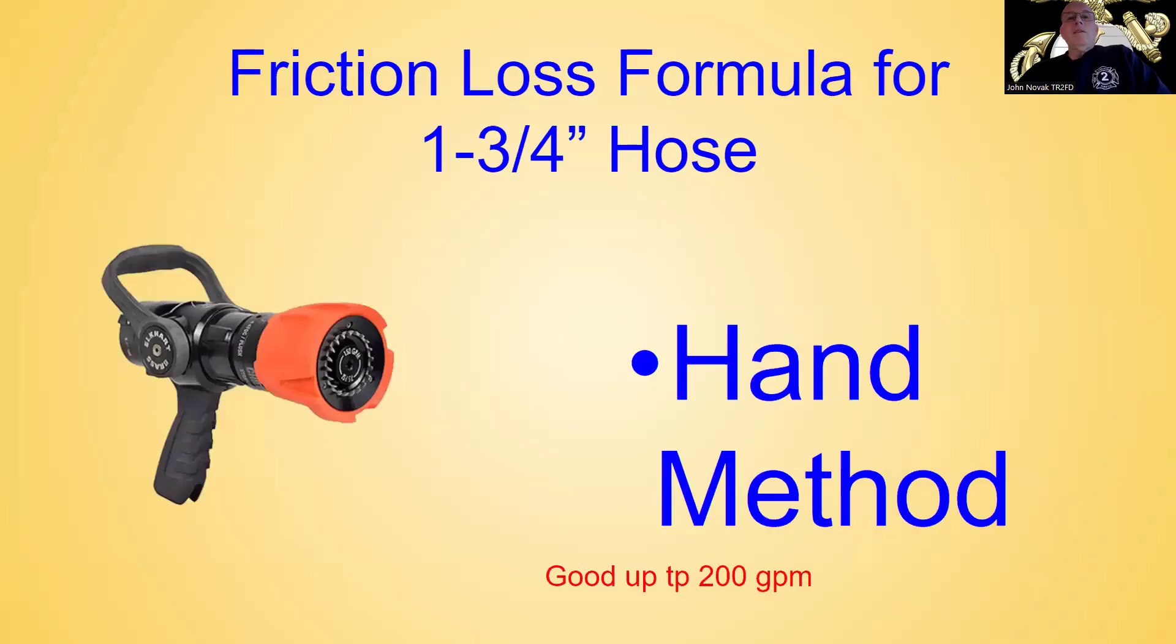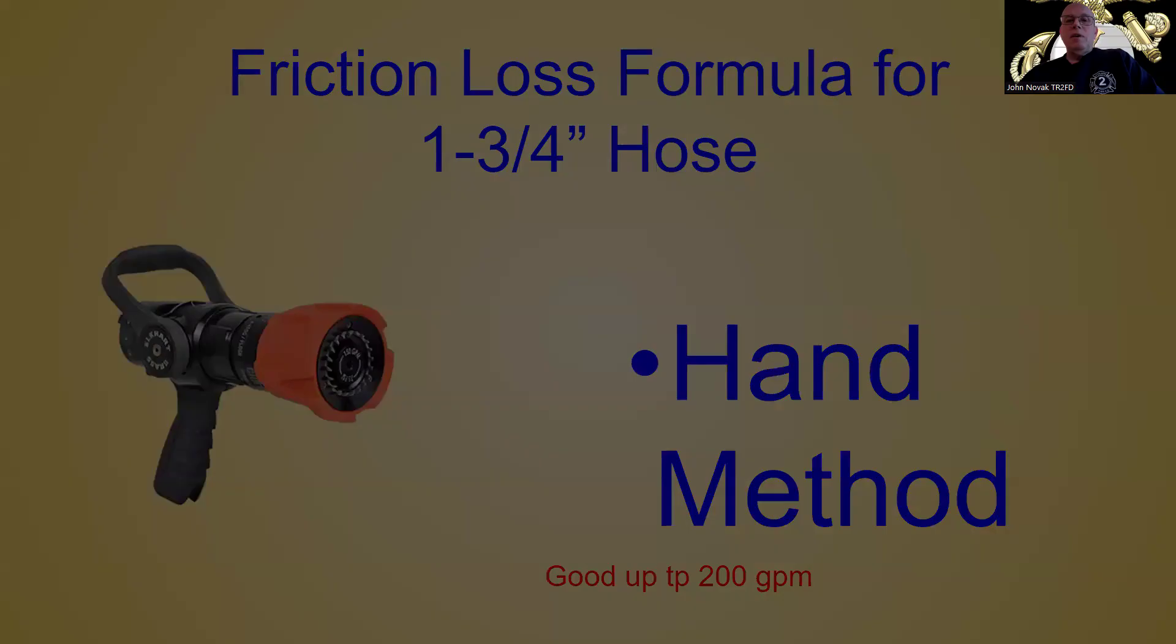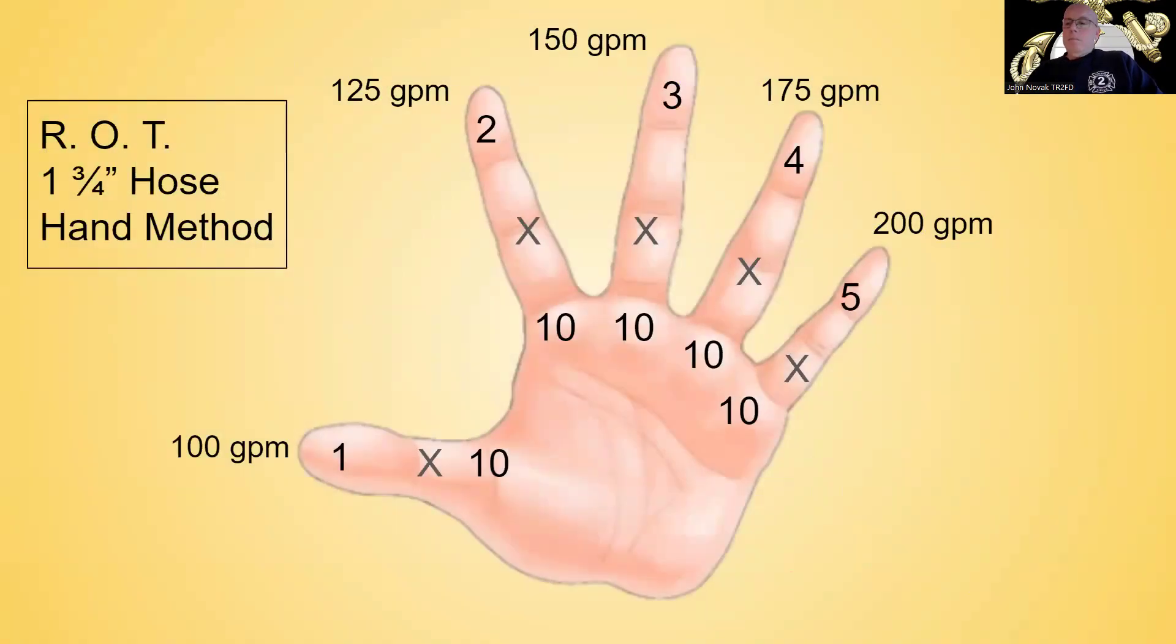By moving to the inch and three-quarter hose friction loss rule of thumb formula, I call it the hand method. It's good up to 200 gallons per minute. So looking at your left hand, we start at our thumb. Our thumb is number one. Index finger is number two. Middle finger is three. Ring finger is four. Our pinky is five. We also assigned different flows to each finger. So the thumb is 100 gallons a minute. It increases by 25 gallons a minute. So index finger is 125. Middle finger is 150. The ring finger is 175. And the pinky is 200.